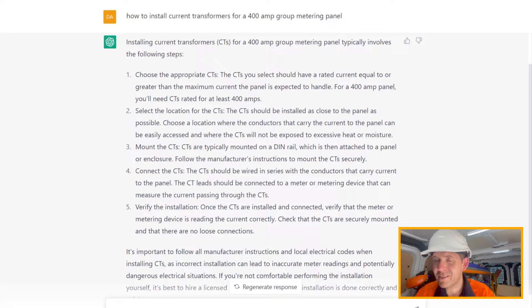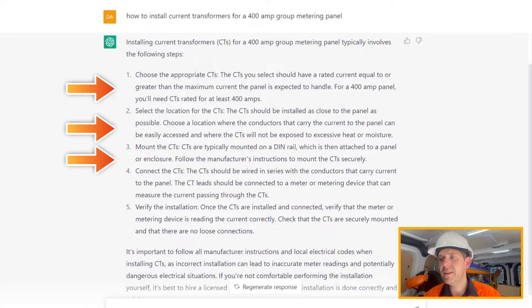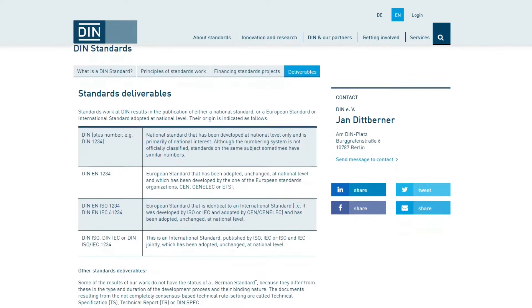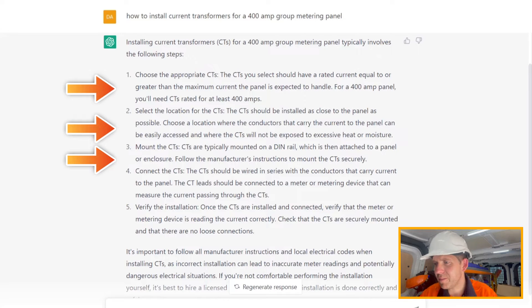Unbelievable. This is interesting — this is kind of cool though. I'm impressed that it was able to create this procedure, but I've got a couple of issues. Stepping through: point one is choose the appropriate CTs, which is obvious. Select location — sure. The next one is mount the CTs. CTs are typically mounted on DIN rail. DIN is actually a standard, and DIN rail comes out of that standard — it's something we mount a lot of electrical equipment on, like circuit breakers. In this instance they're directly mounted, so I really wouldn't be able to follow this procedure. It goes on to say connect the CTs and then verify the installation, which is a really great idea. Let's get into this CT install.